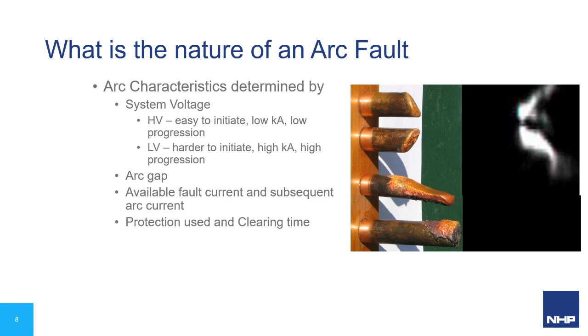for that application. The photo on the right here is from a study where they took some photos of that plasma medium developing over a three-phase fault. You can see the actual arcing across from that second peg to the first and third, and a little bit of remnants on the bottom one there. So you can really see that plasma arc pretty clearly in that image.